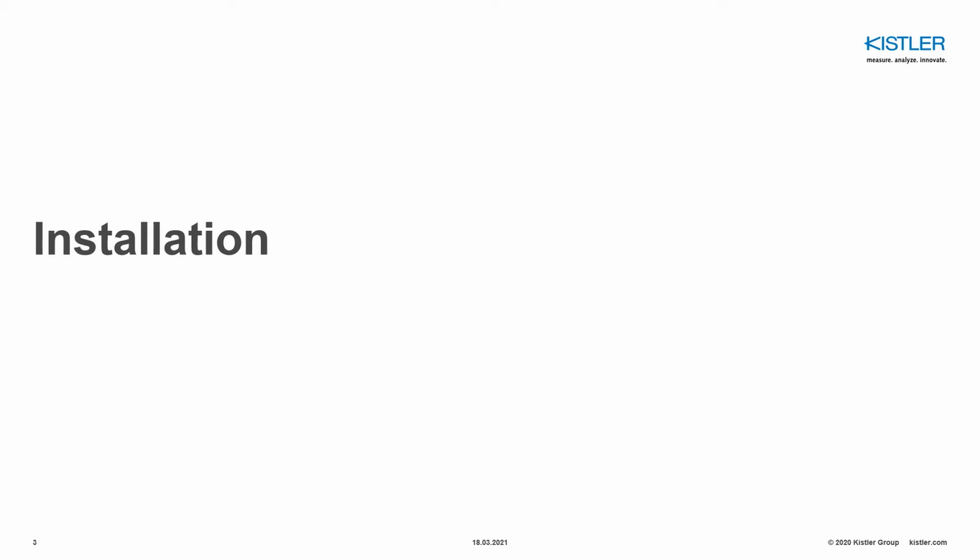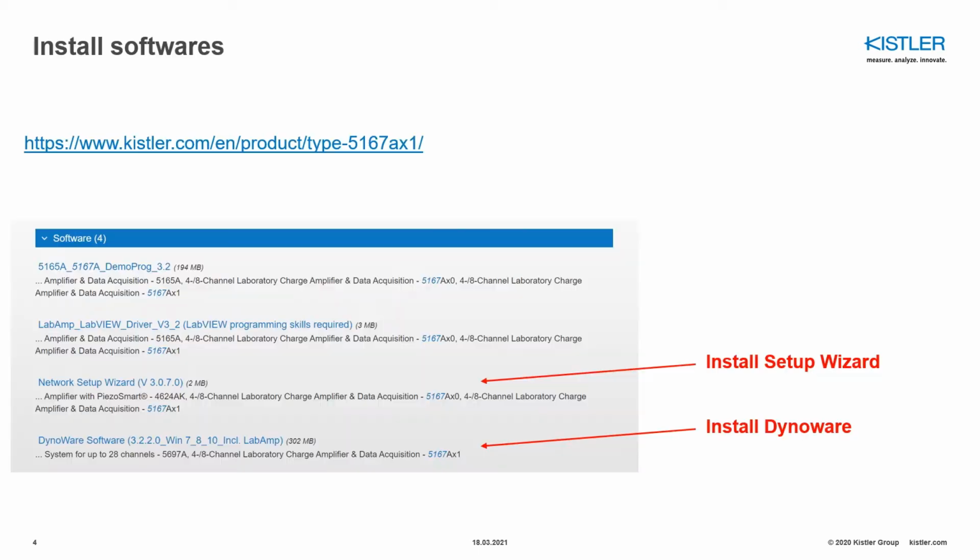Let's start with the installation. So we will start with installing the required software. You can find them on our web page under the products, and then you go to the 5167, which is our LabAmp that we utilize. You will install Network Setup Wizard and also the Dynoware software, which I will explain later on.